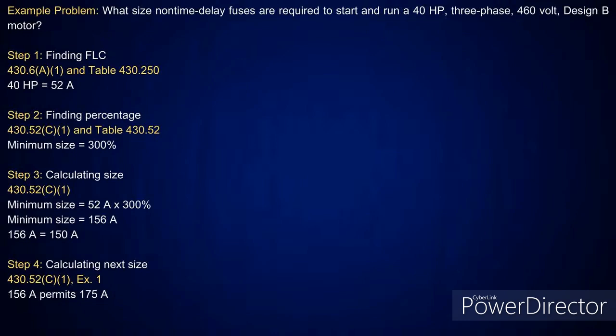Now, I'm going to be doing a non-time delay fuse, and it's a 40 horsepower, three-phase, 460 volt design B motor. I said you're going to start at 430.6(A)(1), which tells me if I'm sizing the conductors and overcurrent device, then I can go look at one of the tables. If you were doing your overload protection, you would be looking at 430.6(A)(2) and you'd use the nameplate value. But for this, you're going to use the table value for sizing your conductors and overcurrent device.